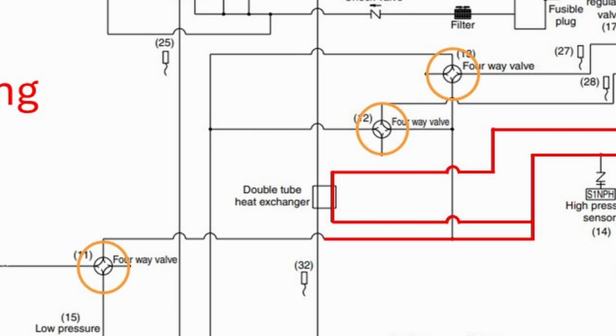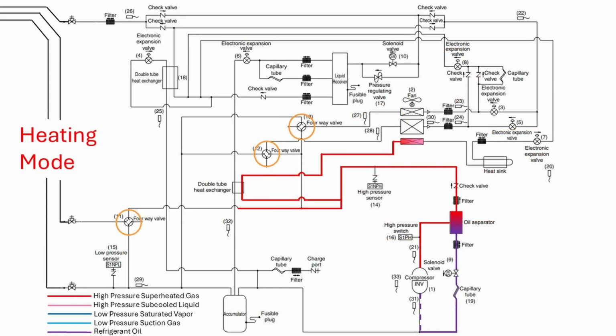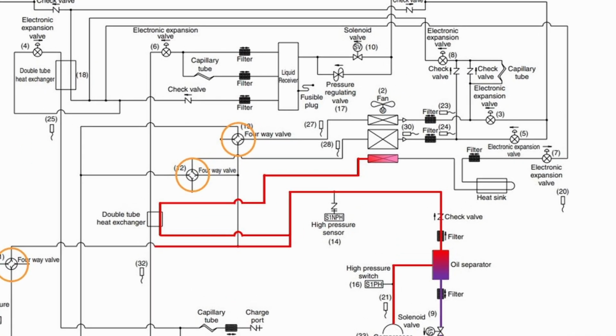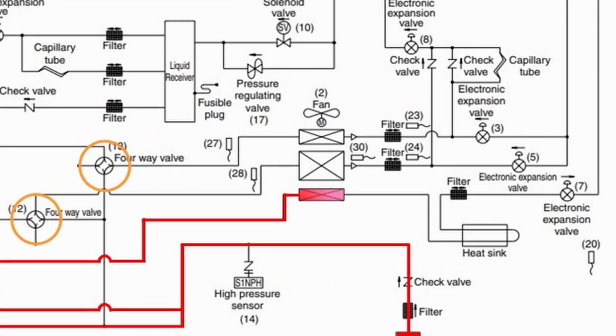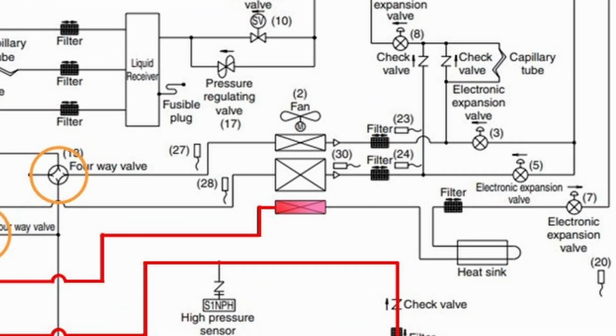Notice that this particular diagram has 3 four-way valves. Also notice that the outdoor unit heat exchanger is divided into 3 separate compartments. So in this type of system, the 4-way valves not only control the mode of operation, but they also control the capacity of the system by regulating the amount of refrigerant through the outdoor heat exchangers. So the system only uses the amount of outdoor heat exchanger needed.